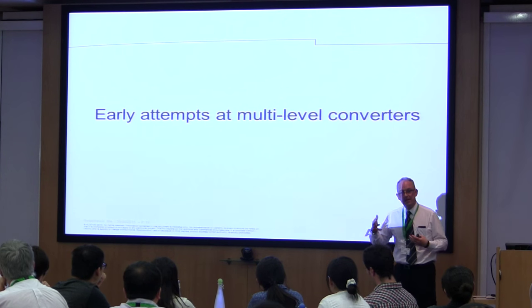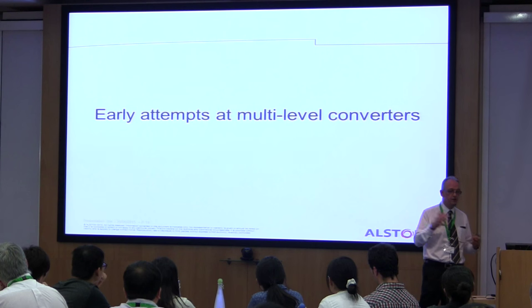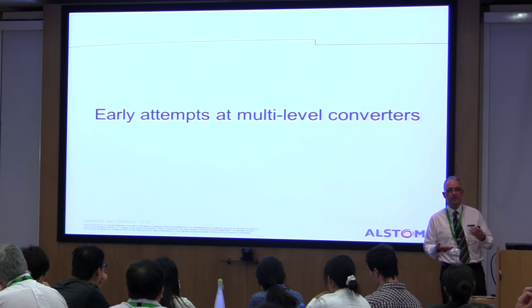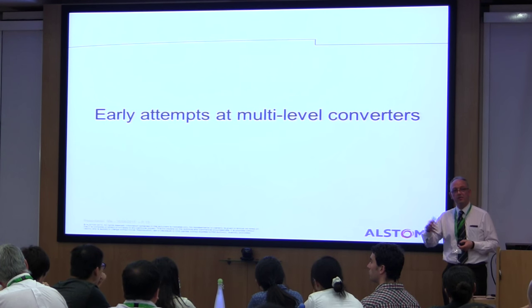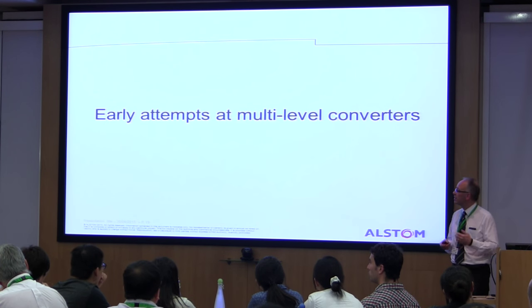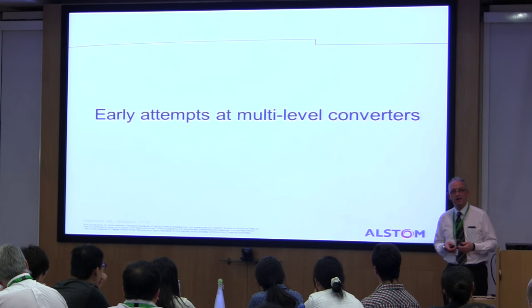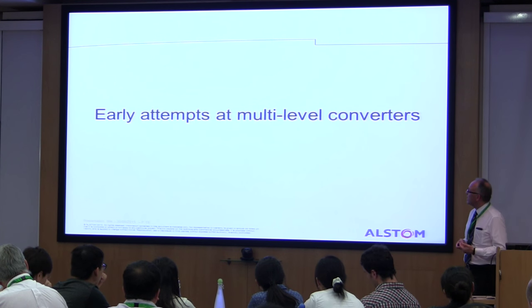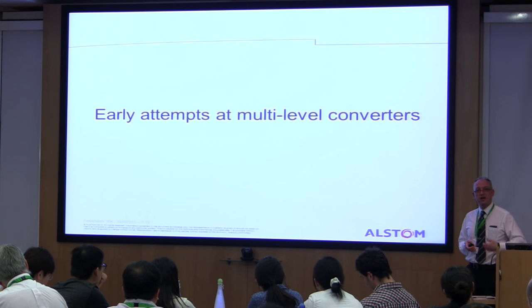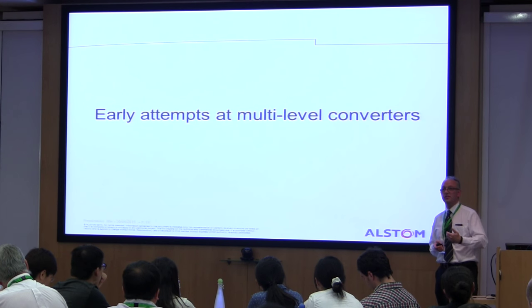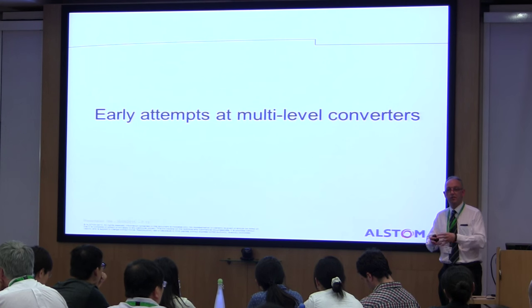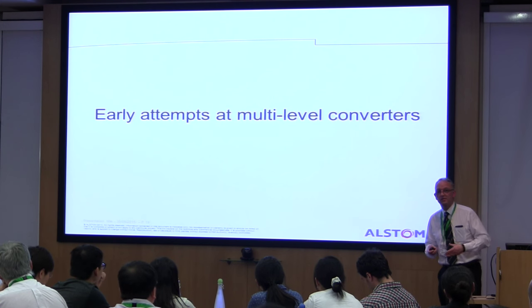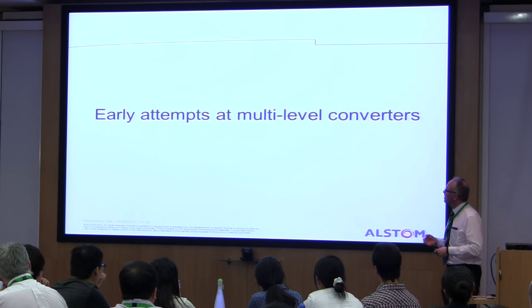That was always seen as a problem. In terms of losses, the original early schemes were around 4–5% loss. With a two-level converter using optimal pulse width modulation, those losses came down to about 2.5% — still quite high — and you still have the complexity of high switching frequencies and the electromagnetic disturbance impacting control and other components.